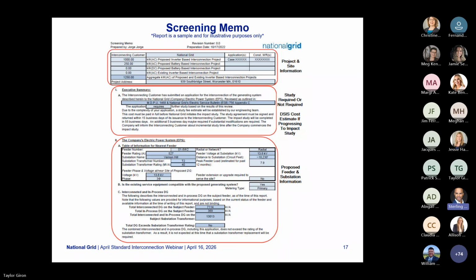The first page is laid out in three sections, with the top section showing the proposed project and site information. The second section will detail whether the project will require further study or not. If the project does not require further study, it could progress to conditional approval or supplemental review. If the project requires further study and is progressing outside of a group study, this section will include an estimate for a system distribution impact study. The third section outlines the feeder information, substation information, and total amount of proposed and interconnected distributed generation on that feeder and substation.